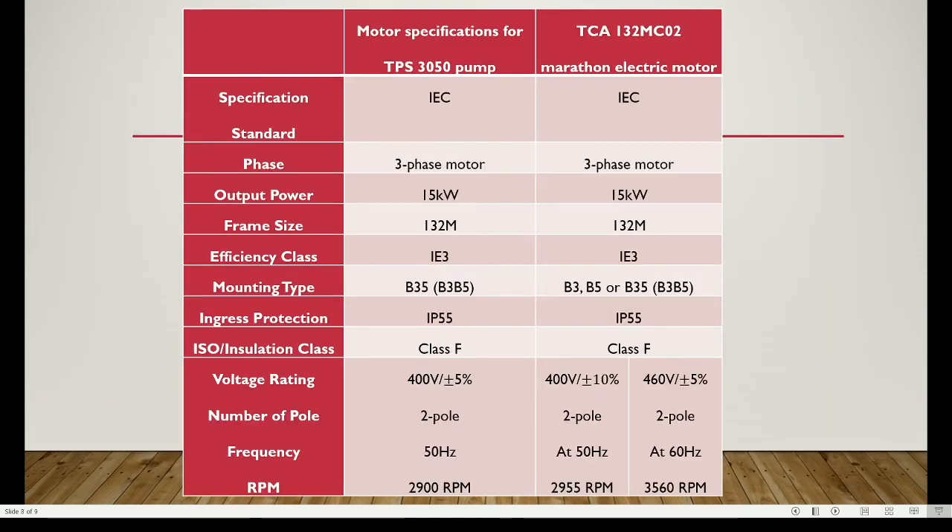From the comparison table, the motor has IEC standard and is a three-phase motor giving 15 kilowatt output power. The frame size is 132M, efficiency class is IE3, mounting type is B35, ingress protection is IP55, and insulation class is Class F, meaning the maximum temperature of the motor winding is 155 degrees Celsius. At 50 hertz, the voltage rating is 400 volts rotating at 2955 RPM. At 60 hertz, the voltage rating is 460 volts rotating at 3560 RPM.